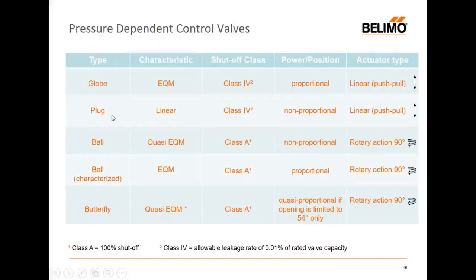Then on some PI valves, we see plug control. These tend to have a linear characteristic. They're still pressure independent, but they're linear, and they're usually a little bit short stroke. And they too are class 4 shutoff, and they are not proportional. So they won't give us the proportionality that we need from EQM, but we still see them in the market. And this is why we're stressing the point about choosing EQM valves. And they too are linear actuated push-pull on an electromechanical actuator.